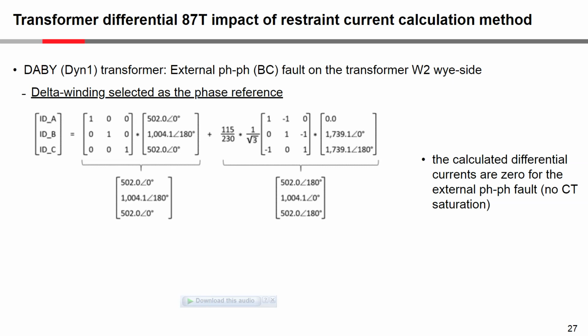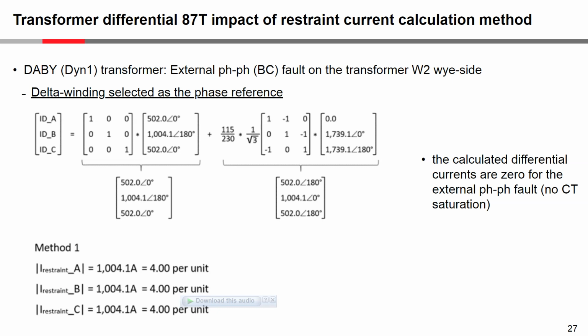phase reference. So when we calculate the compensated currents, you can see that in each phase, if you were to add them, they would sum to 0, and that is what we would expect because it's an external fault. But if we now look at the calculation of the restraint quantities, you can see that method 1 looks at the maximum current and applies that to phases A, B, and C. So if we look at those 6 compensated currents, you can see that 1004.1 is the maximum, and so that would be the chosen restraint current for all 3 phases.